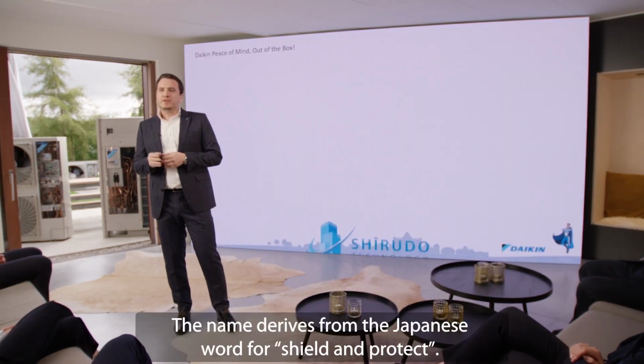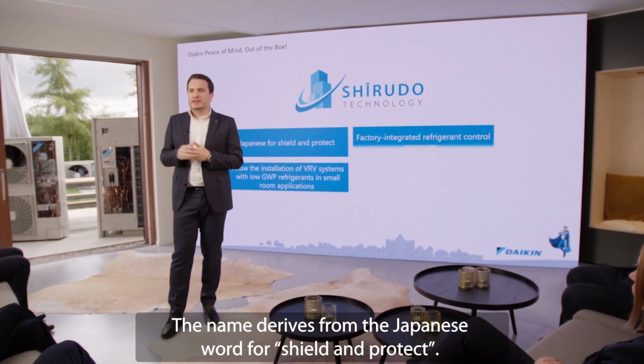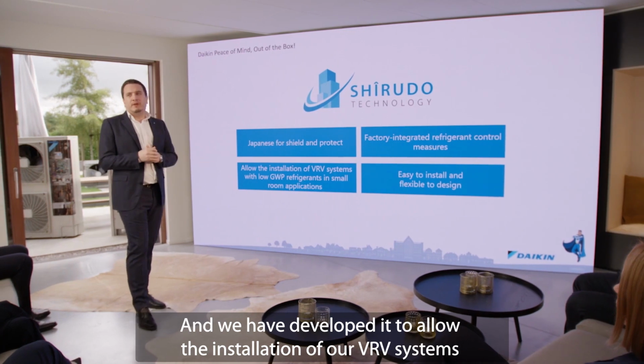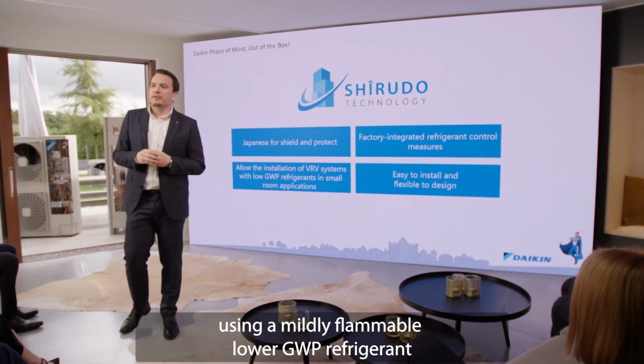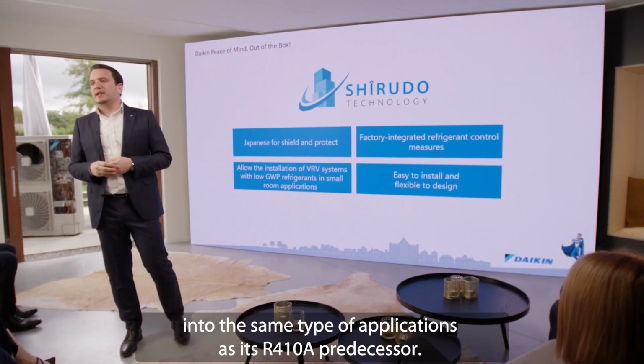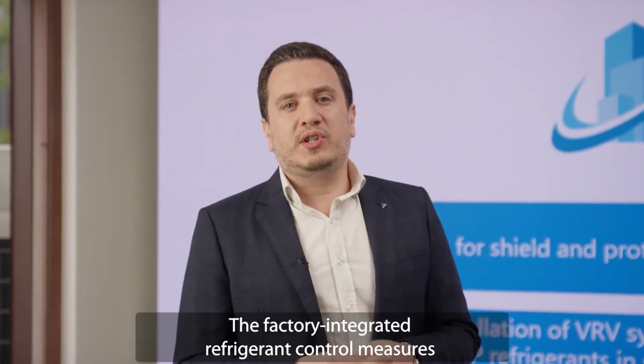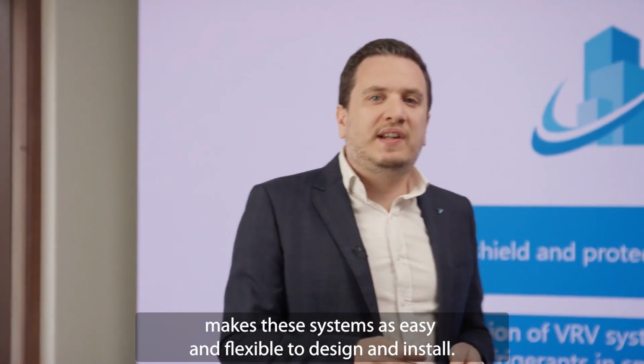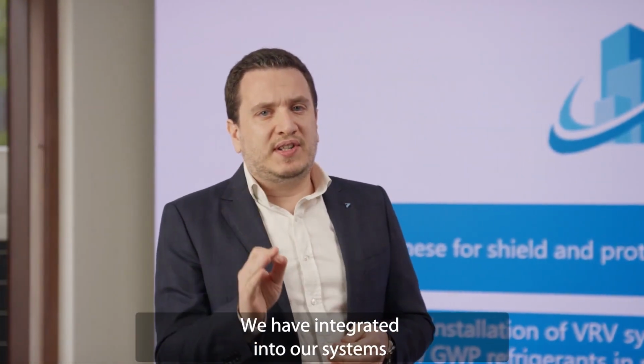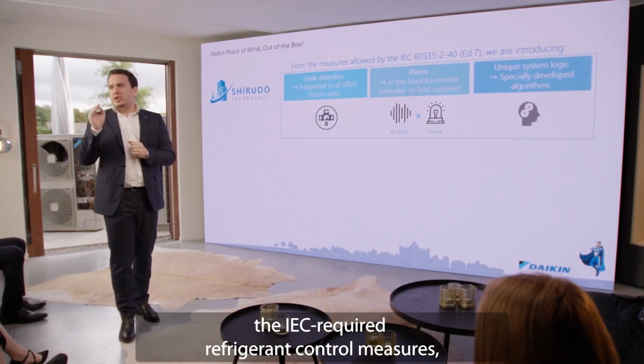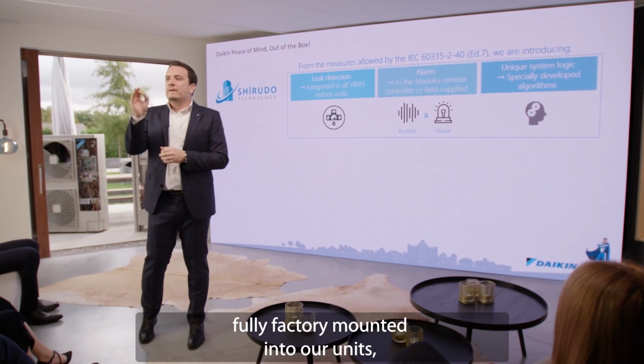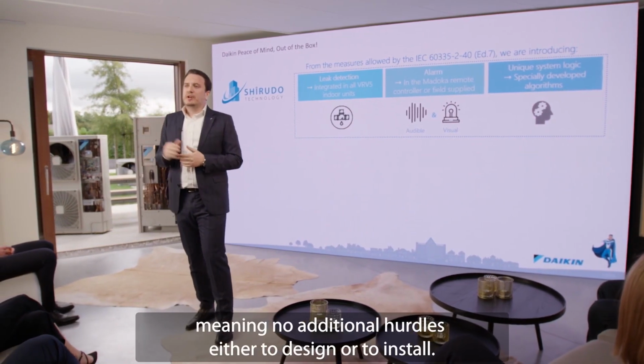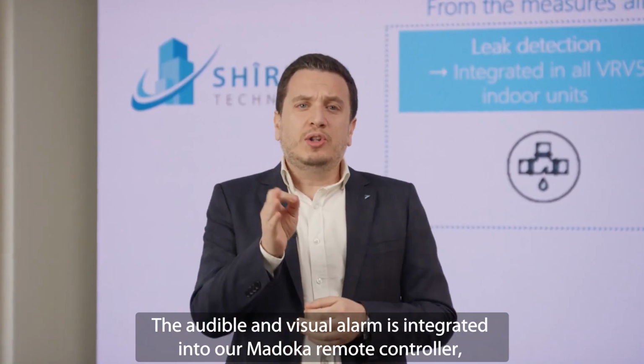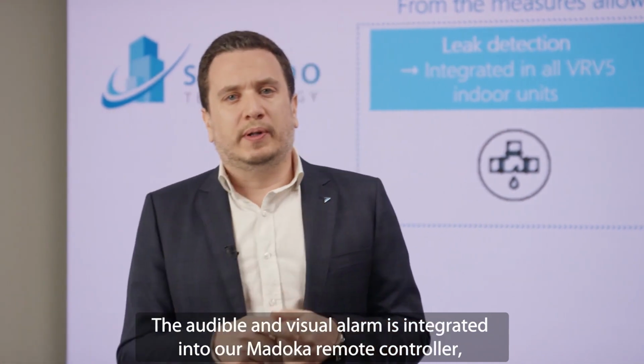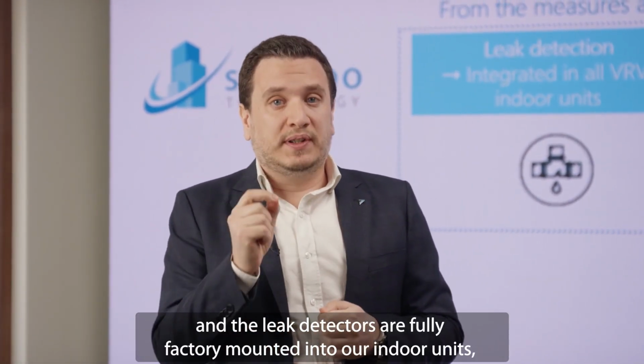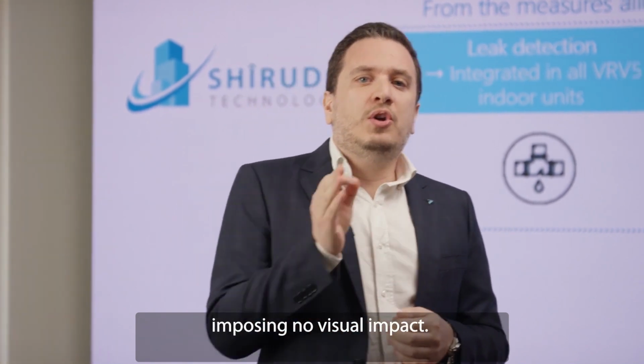Why Shirudo technology? The name derives from the Japanese word for shield and protect. And we have developed it to allow installation of our VRV systems using mildly flammable lower GWP refrigerant in the same type of applications as its R410A predecessor. The factory-integrated refrigerant control measures make the system as easy and flexible to design and install. We have integrated into our systems the IEC-required refrigerant control measures, leak detection and alarm, fully factory mounted into our units, meaning no additional hurdles either to design or to install. The audio and visual alarm is integrated into our Madoka remote controller, and the leak detectors are fully factory mounted into our indoor units, imposing as well no visual impact.